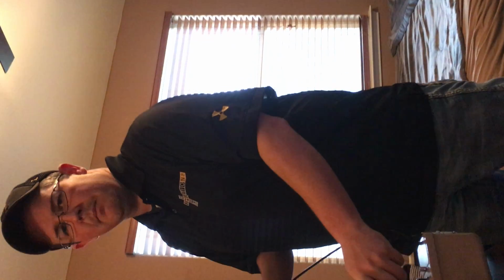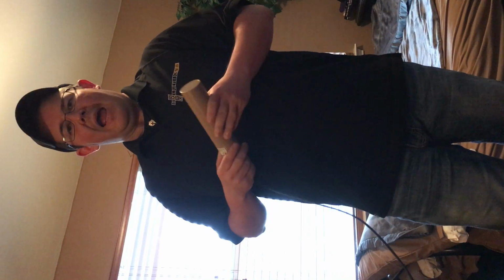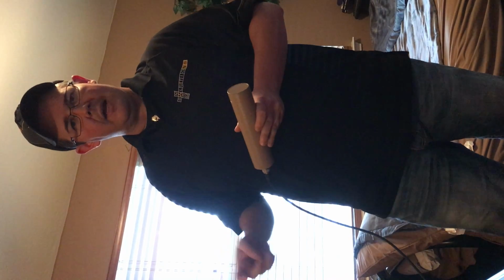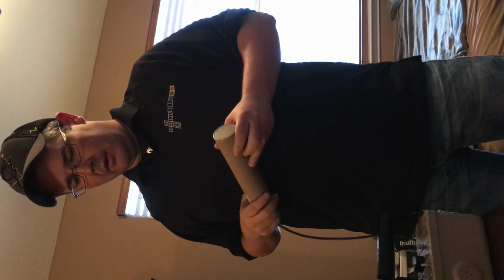Now, keep in mind, I'm making sure that I take as much caution as possible to not whack the probe on the equipment. Now, with the scintillation probe, I would actually have to move no faster than 1 foot per second in order to make sure that my readings are adequate and in good standing, okay? And then after I get done, of course, I would have to use a pen, which could also cause some issues with a lot of writing through musculoskeletal disorders, in order to notate all of my information on that equipment. Okay, so that being said, I want to show you, you can lower the probe in order to survey.